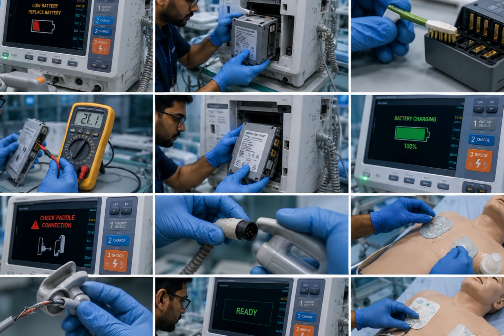The next problem which we might face is a paddle or electrode problem. Here you can see that as well in the image. The machine shows a paddle connection error. The inspection we should make covers paddle cables, ECG lead wires, and connector ports. Check for loose connections, a broken cable, or bent connector pins. Replace damaged ECG lead wires. Apply conductivity gel properly on the paddles. Attach electrodes correctly to the patient simulator. Now the connection warning disappears.